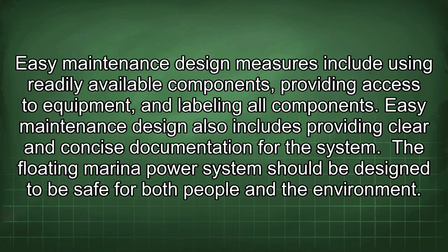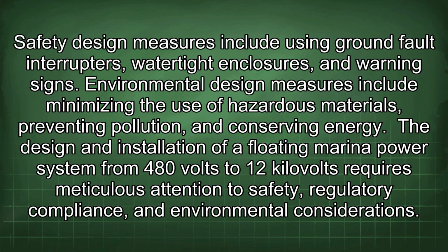The floating marina power system should be designed to be safe for both people and the environment. Safety design measures include using ground fault interrupters, watertight enclosures, and warning signs. Environmental design measures include minimizing the use of hazardous materials, preventing pollution, and conserving energy. The design and installation of a floating marina power system from 480 volts to 12 kilovolts requires meticulous attention to safety, regulatory compliance, and environmental considerations.